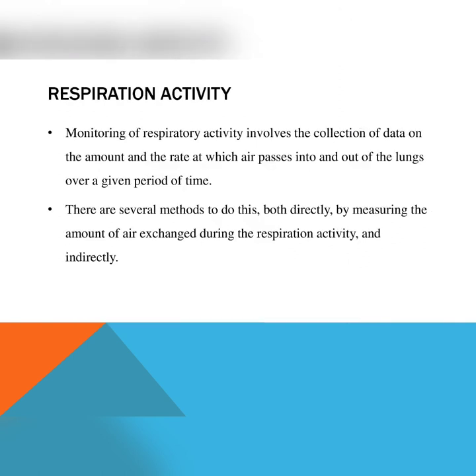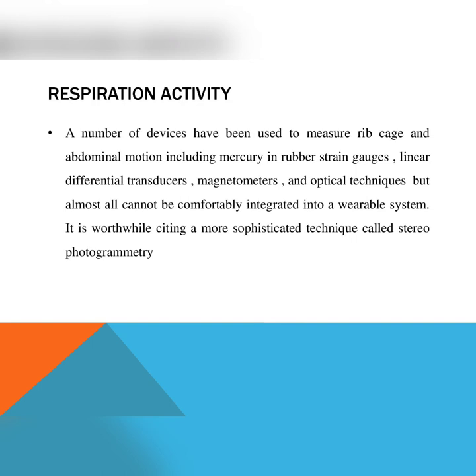Respiration activity monitoring involves collection of data on the amount and the rate at which air passes into and out of the lungs over a given period of time. There are several methods to do this, both directly — by measuring the amount of air exchanged during the respiration activity — and indirectly. A number of devices have been used to measure rib cage and abdominal motion, including mercury-in-rubber strain gauges, linear differential transducers, magnetometers, and optical techniques. However, almost all of these cannot be comfortably integrated into a wearable system.